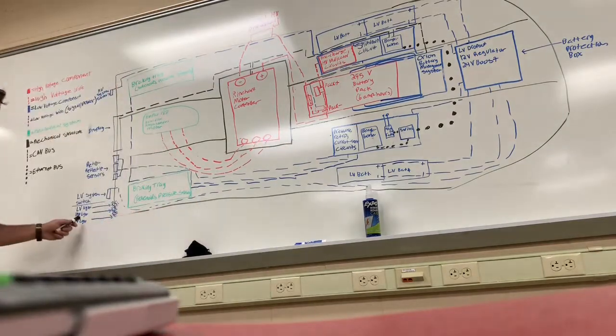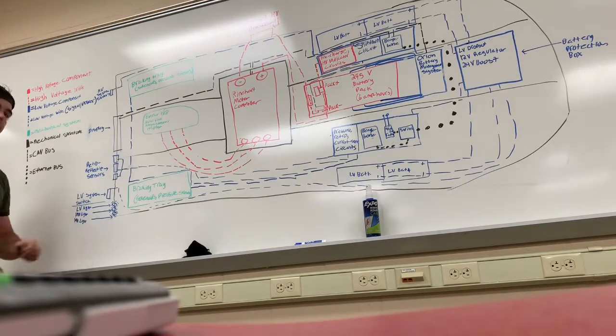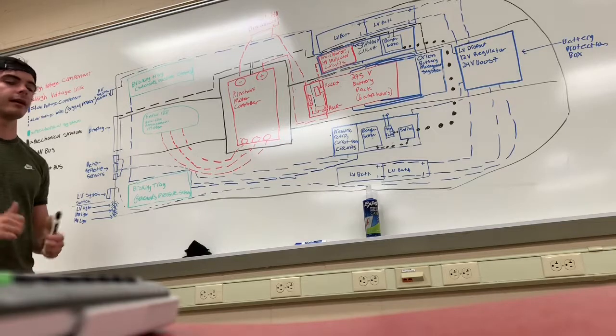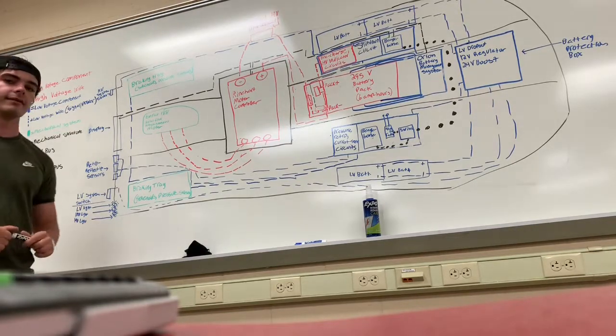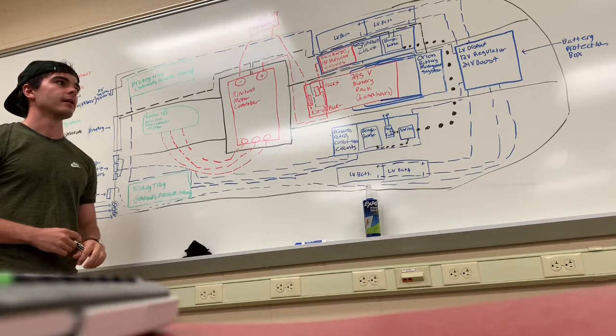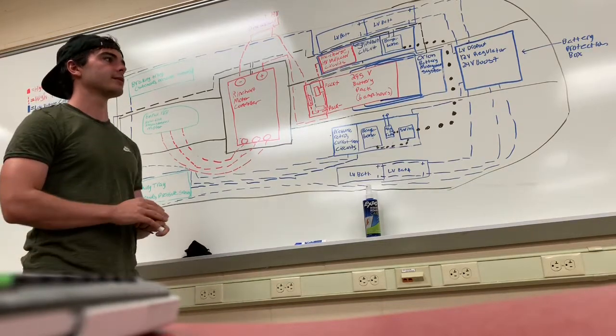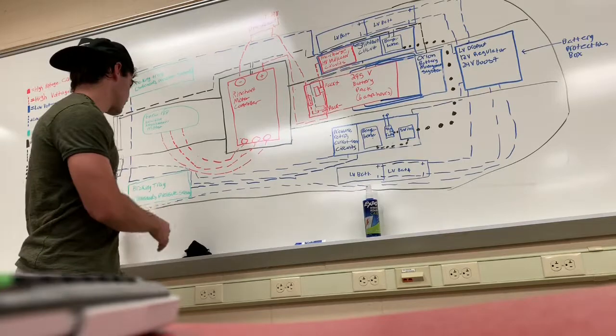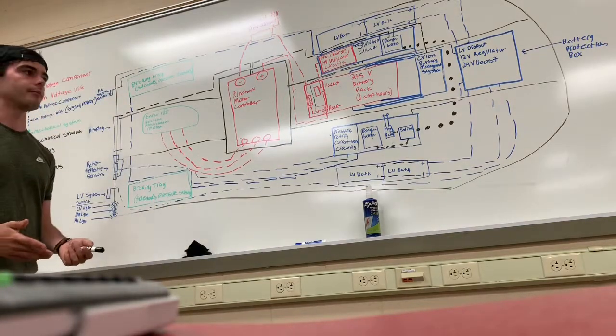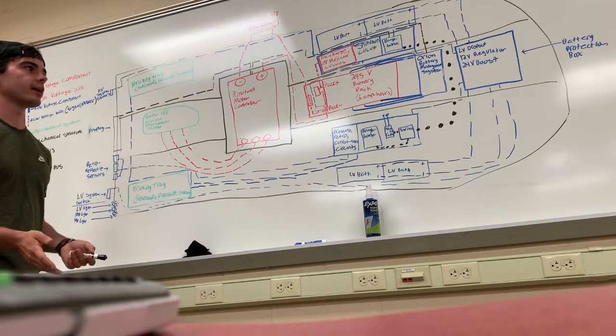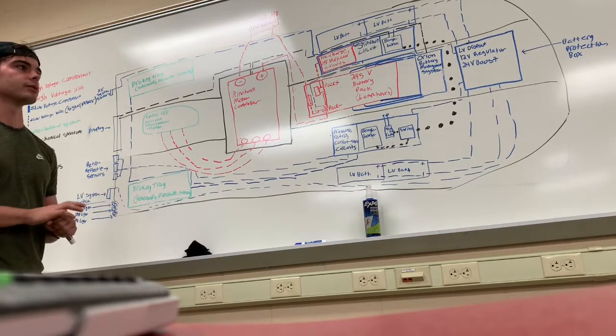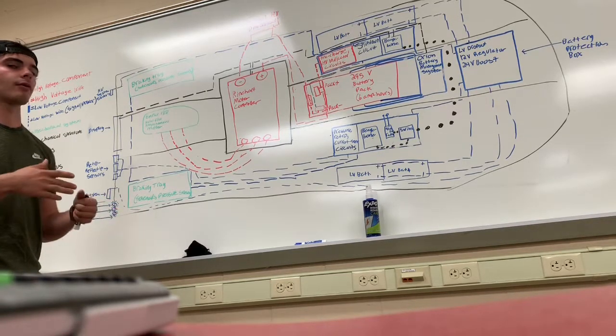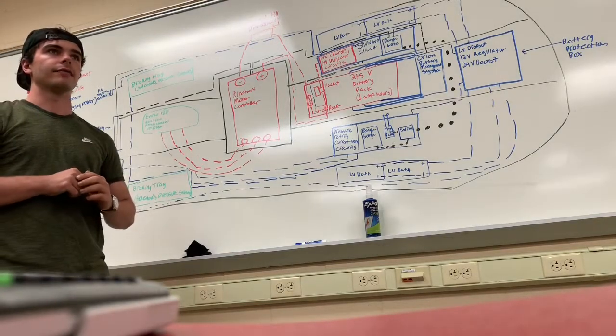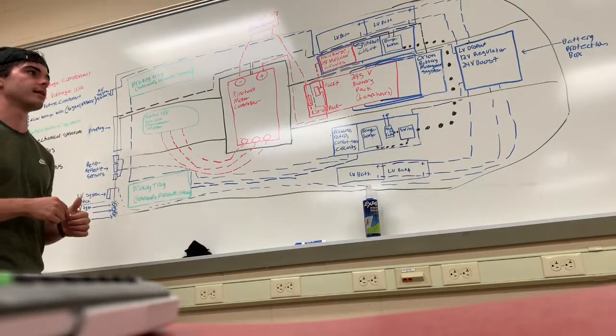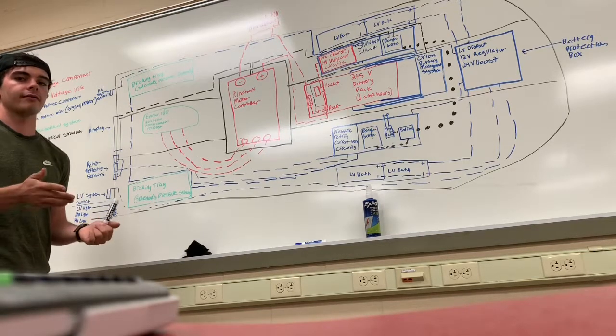It's also used in this light back here. It's simply on if the isolation is in a good state, and off if it's in a fault state. This prevents the case where, say, the light is broken - you still want to approach with safety and check everything is all right, as opposed to the light being powered on in a fault state, where if it goes off you wouldn't know if it's just off or the light's broken.